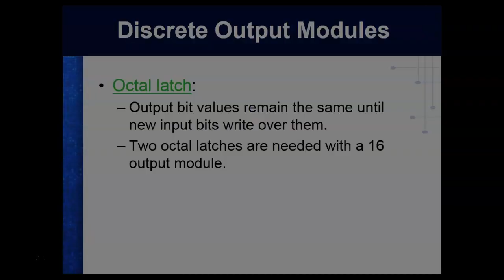So usually inside the PLC operates on 5 volts, but we can put in a lot bigger voltages into these things than we need. The standard now, by the way, you won't hardly see, 24 volts is pretty standard. So we got 5 volts right here, we got 24 volts over there. So what they do is they just put a Zener in there and they just flip it down to 24, from 5 volts to 24 volts.